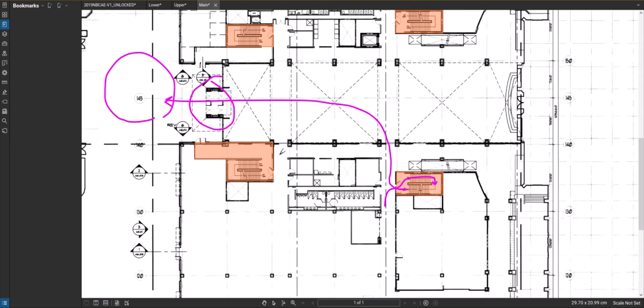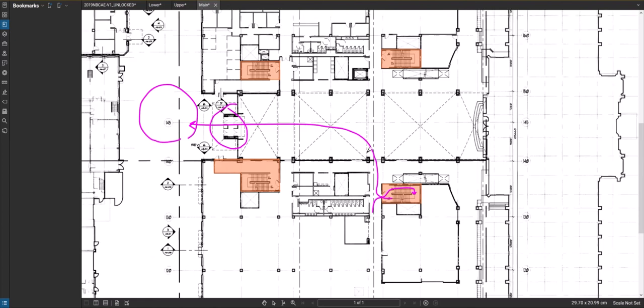And again, what drove that decision is probably travel distance. Again, if you deleted these, if not deleted them because you need them from above, but if you say you didn't have the doors here and didn't use them as part of the exits, then you'd have double the amount of exterior doors leaving the building, because again, it's based on occupant load.